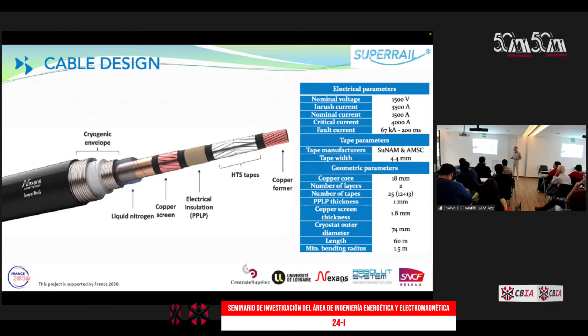Again, this is the layout, and this is a very technical view of the termination. This part is very technical because when you cool down the cable, the material contracts, and over tens or maybe hundreds of meters, this contraction due to the cool-down may reduce the length by a few centimeters. So this system has to be able to compensate for the variation in length. Typically, it is placed on something that can move, so we can compensate for the length change during contraction. You can see here the connection plate from room temperature to the conventional cable on the outside.